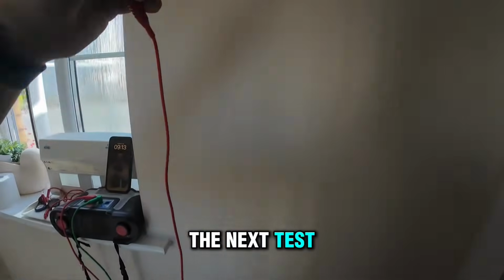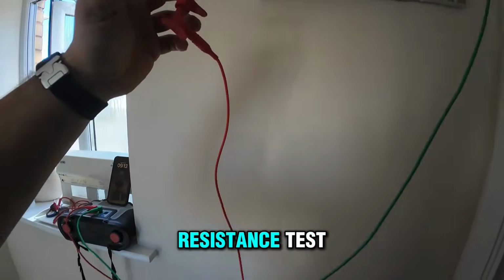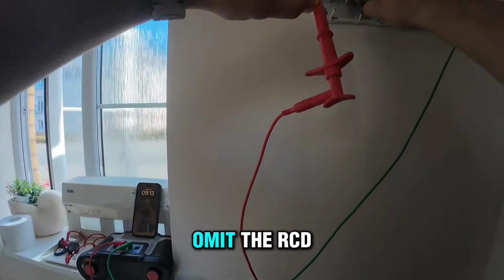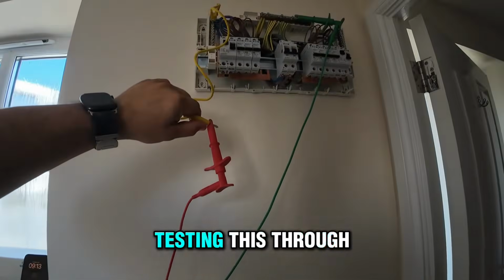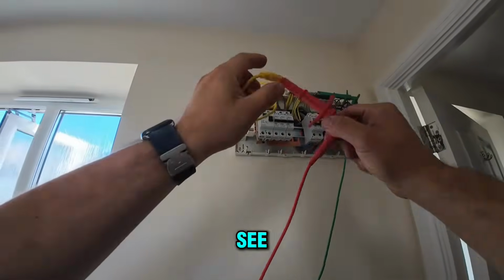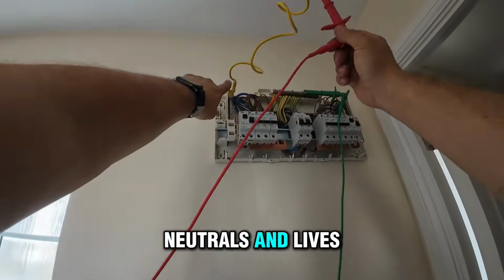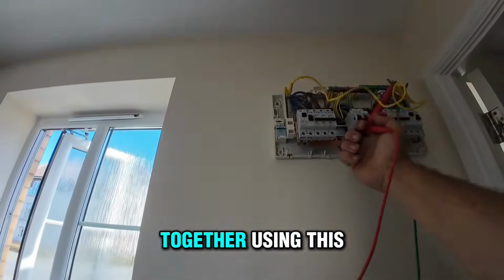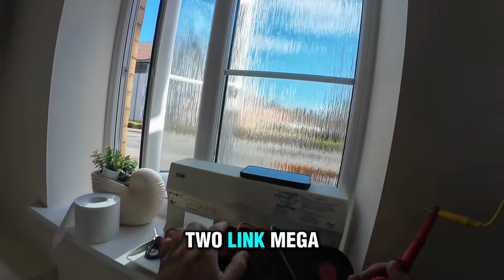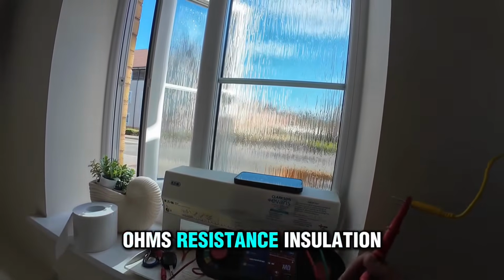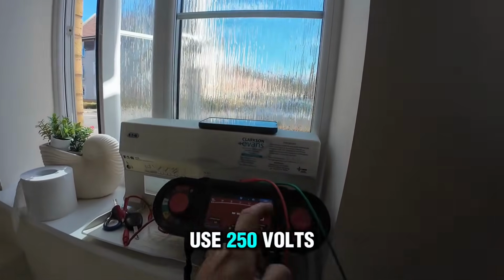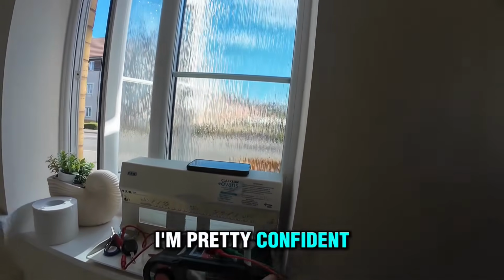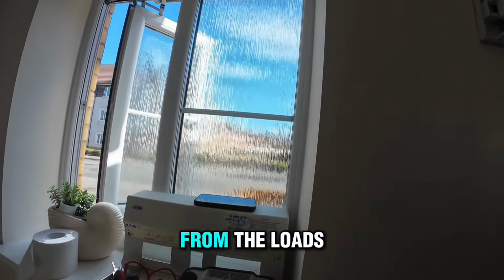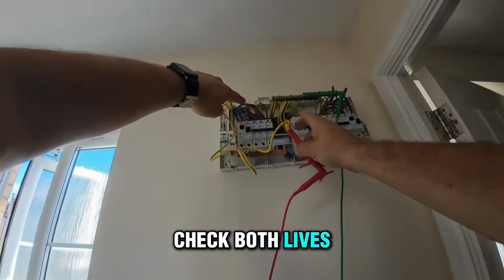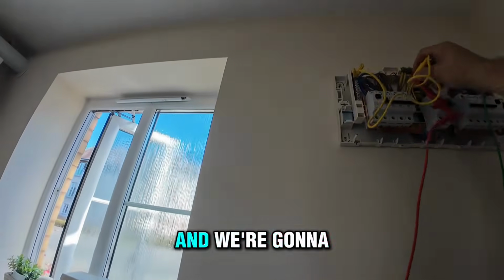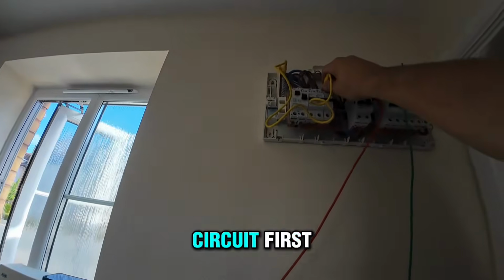The next test I'm going to do is the insulation resistance test on the whole board. I'm going to omit the RCD just to make sure I'm not testing this through the RCD. As you can see, neutrals and lives will be connected together using this R1, R2 link. Megaohms insulation resistance, and we're going to use 250 volts. I'm pretty confident we've removed everything from the loads, but we'll double check. Both lives to earth, and we're going to start from this circuit first.